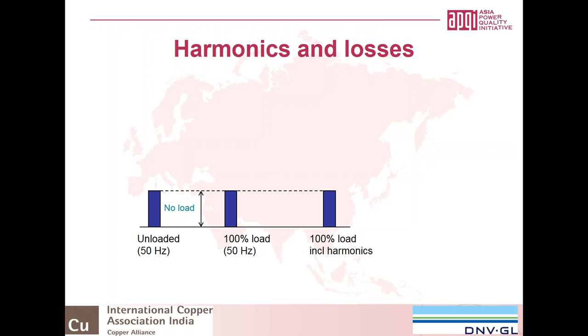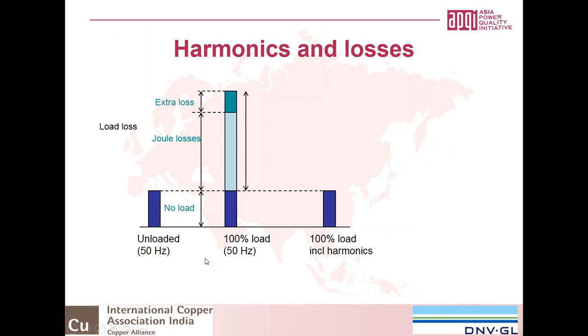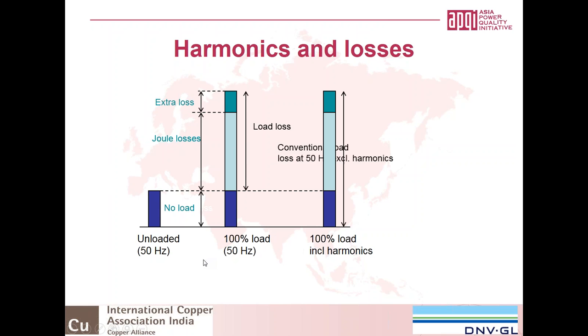What is happening in the transformer? In this case I will show you a picture of an unloaded transformer at 50 Hertz. Normally you will have a no load situation, and for me it doesn't matter if the transformer is unloaded, loaded 100%, or loaded 100% including harmonics in the current. If you are loading the transformer for 100% without harmonics, you will have the Joule losses within the transformer, the DC losses, and also additional losses, the extra losses.